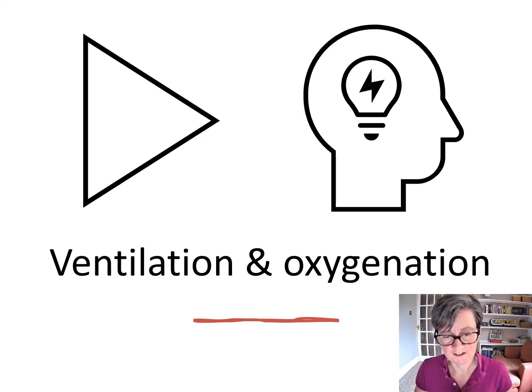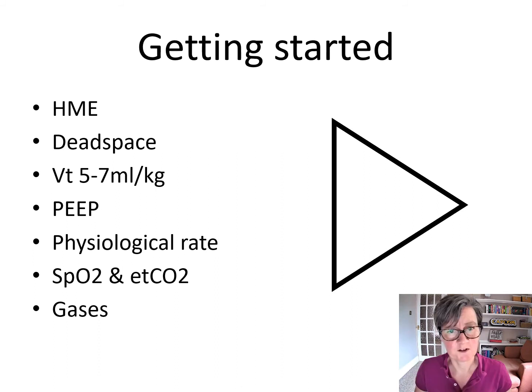Now we come to ventilation and oxygenation once your ET tube is down. This might cause some problems initially, so what I want to talk to you about is firstly getting started and then troubleshooting problems. Don't forget to use a heat moisture exchange filter. When you get started, think about the compliance of your circuit and minimise the dead space. It's fine to use pressure or volume control in an infant or child. We normally aim for tidal volumes of 5 to 7 mils per kilo. I would say aim on the generous side to start with, because you've probably got a little bit of recruitment and catching up to do.